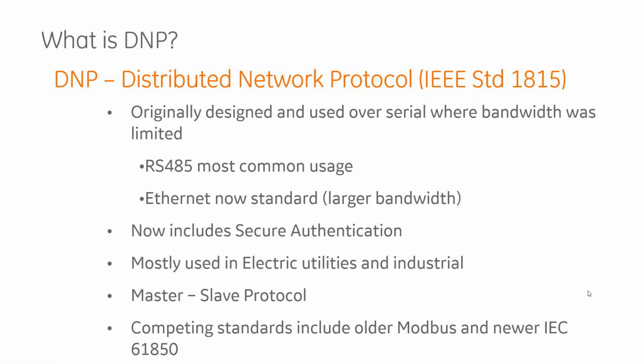So not to say that you have to use DNP in a serial, but it was built initially for serial communication. That was its basis. It now includes secure authentication, so you can authenticate and get the data securely. It is mostly used in electrical utilities, somewhat in industrial, but it's more electrical utilities. It's a master-slave or client-server protocol, so you have the SCADA that needs to talk to multiple slaves. Some of the competing standards for our applications are Modbus and IEC 61850, which are the main ones.